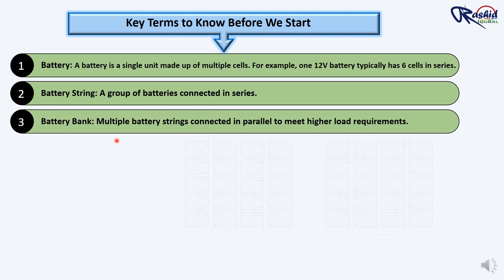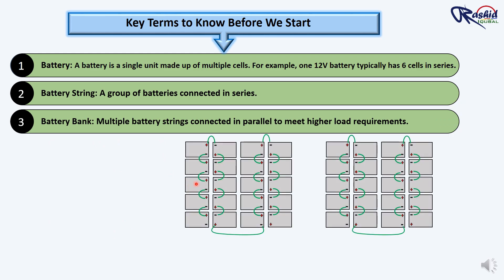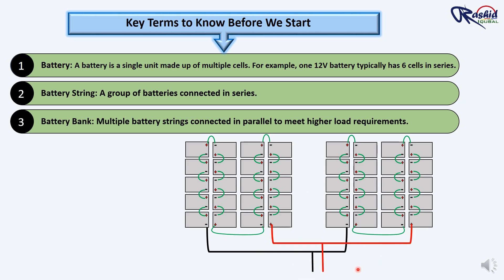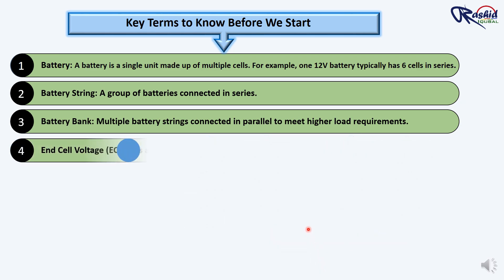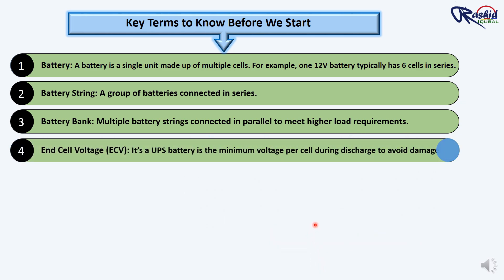Third: Battery bank. A battery bank is created by connecting multiple battery strings in parallel. This increases the overall capacity of the system while maintaining the same voltage. If you need to power a larger UPS or load, you can connect several battery strings in parallel, which allows for more energy storage to meet the demand.